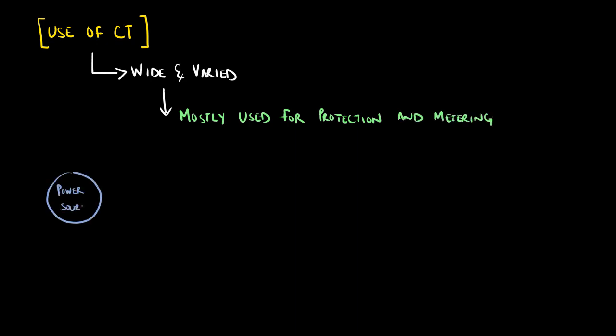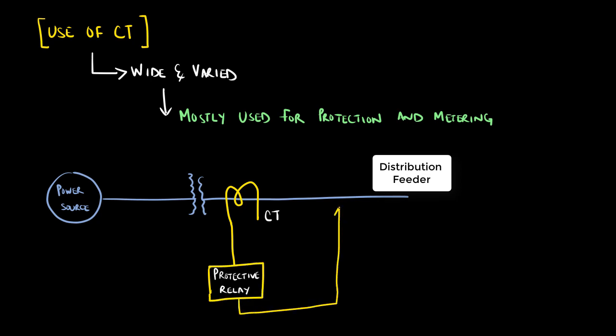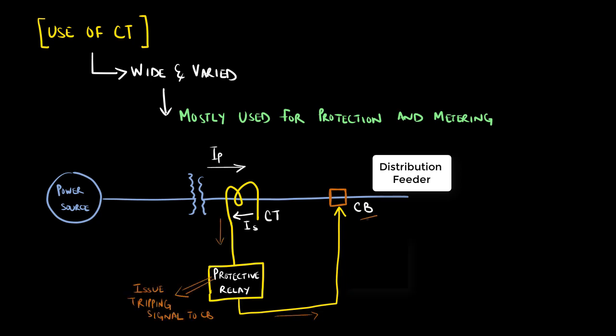In order to protect a distribution feeder, a current transformer can be wired to provide current quantities to a protective relay. If an abnormality occurs, the primary line current would increase, which is transformed to secondary values. This increase in current would indicate an abnormality, and the protective relay would issue a trip command to a circuit breaker.